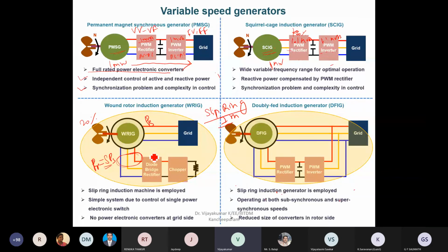So what is my converter rating? If I'm using a 1 MVA machine, what is my converter rating? 20%, because I'm operating in a 20% slip range. So you can use 200 kVA, that's the max converter rating required at the rotor terminals. So the converter ratings are less than the machine rating. Even reducing the converter rating by 10% is a huge saving in the system cost. That is the advantage we have with the wound rotor induction generators.